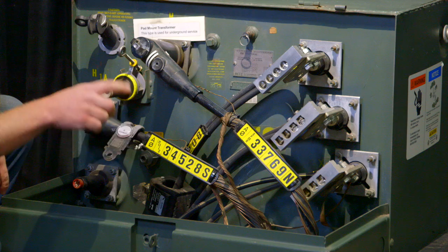To give you a brief rundown on how these work: we've got overhead power lines through your neighborhood, and underground wire that attaches to the overhead power lines. It comes in here at 7,200 volts, goes through the back of the transformer through some coils, and creates a secondary voltage, which is 120 volts and 240 volts. That goes into your house. This also comes in from the pole and goes out to another transformer - we can go for miles from transformer to transformer to transformer.